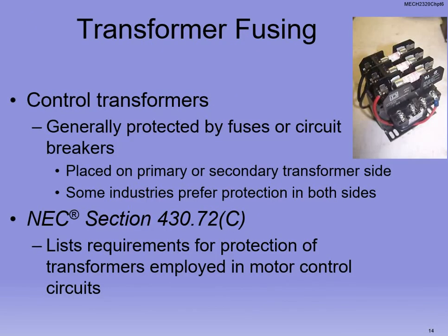Okay, we can also protect the transformer. We protect everything, whether it's with the breaker, overload relays, all those different things. So you'll notice when you open up a control panel or things like that, the transformer will also have fuses on it. And this is much more practice on the larger voltages and things like that. But you'll see that there's a fuse for each line. Okay, they're placed on either the primary or the secondary.